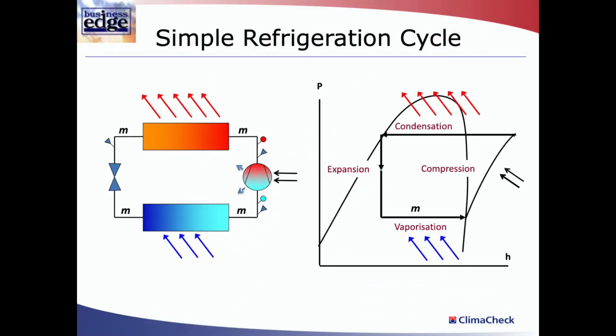So, with the measurement of those parameters, ClimaCheck is then told what refrigerant is being used. It deals with 60 or 70 refrigerants now, including blends, and it can then plot and work out on the pressure enthalpy chart for that refrigerant every aspect of your system's behavior. So it knows the enthalpy at every point. With the power input to the compressor, it can calculate the refrigerant mass flow and then tell you exactly what your cooling capacity is, heat of rejection, power input, power factor, volts per phase, amps per phase, and literally every parameter.